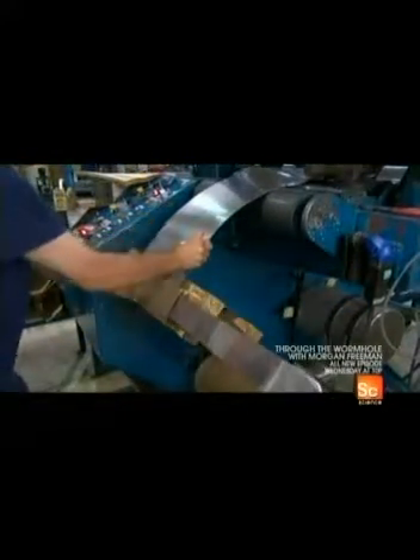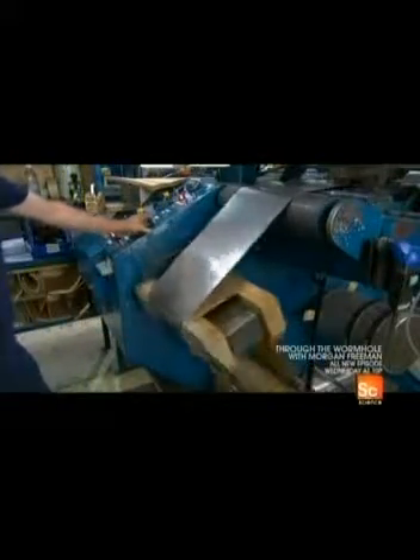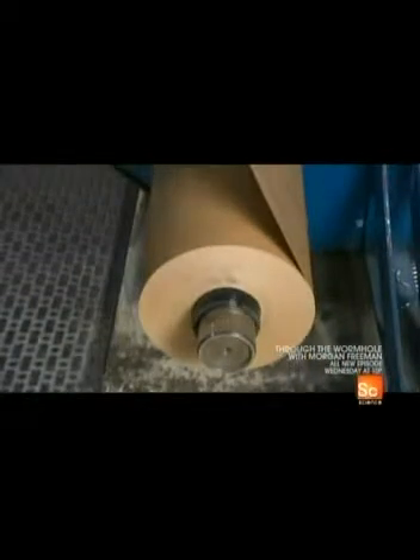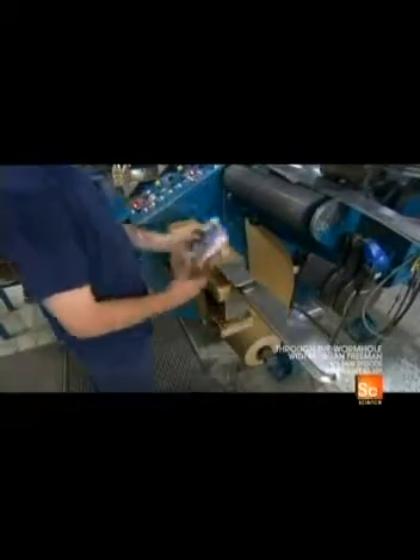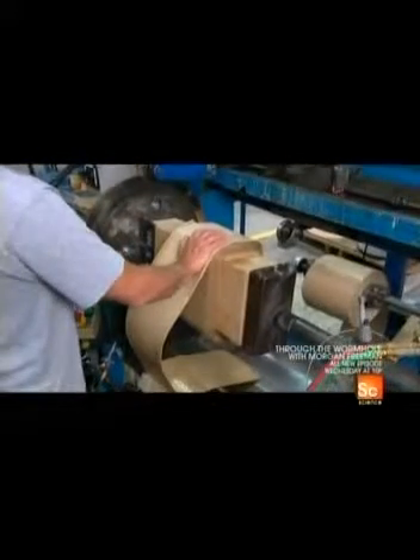Aluminum is a metal that can withstand the heat that a high-voltage current produces. As the block is rotated, the paper and aluminum strip are wrapped around it. An aluminum bus bar called the low voltage lead sends low voltage current out from the transformer. Workers fold the lead and move the unit to another rotating block for more wrapping. The insulating paper has epoxy glue on both sides — this glue will later melt and bond several components in place.